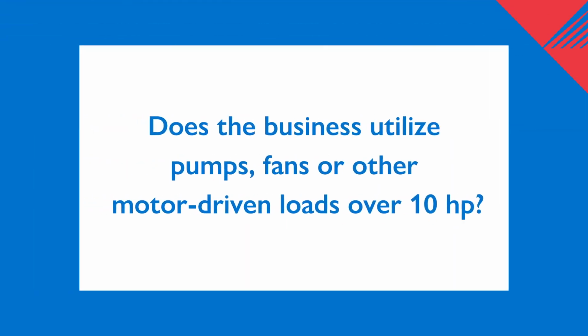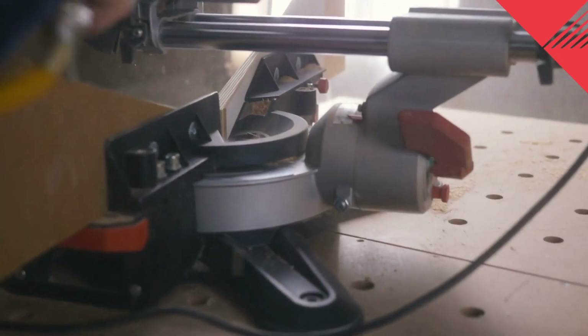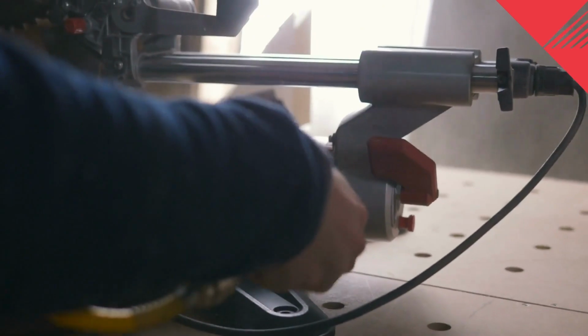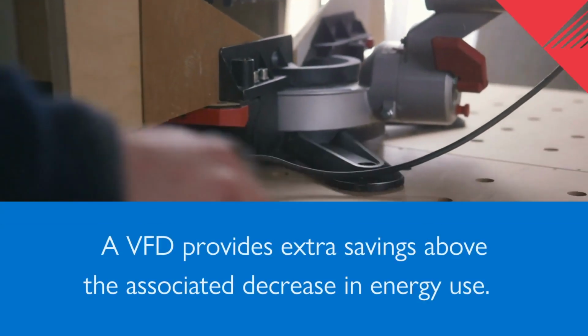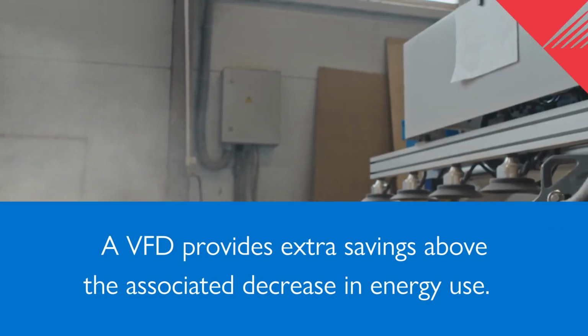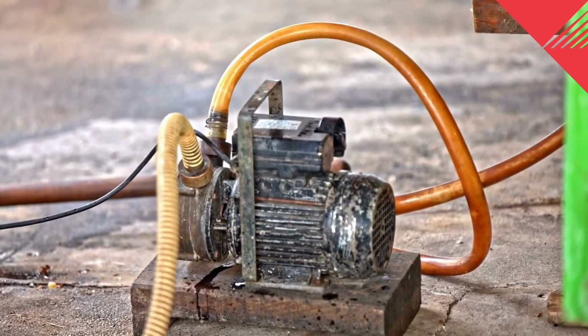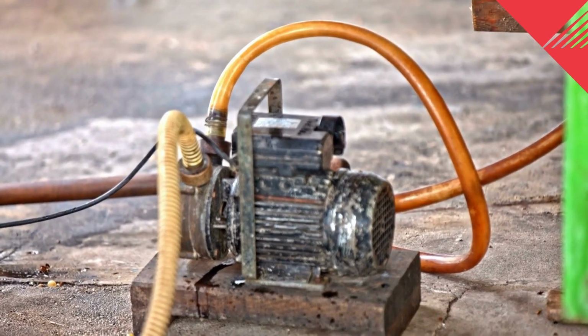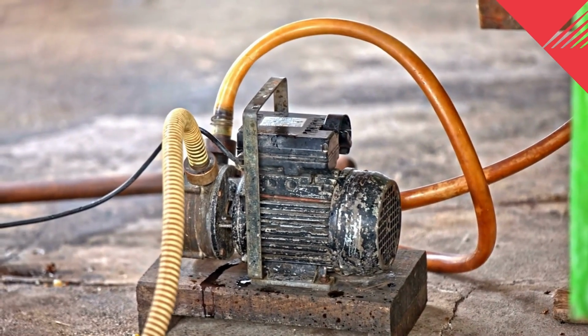Does the business utilize pumps, fans, or other motor-driven loads over 10 horsepower? Like compressors, the frequent starting and stopping of these items uses a lot of energy. A VFD slows and accelerates the motor, making the entire system more efficient for extra savings above the associated decrease in energy use. When it comes to pumps, a VFD senses and maintains pressure, which reduces water waste too.